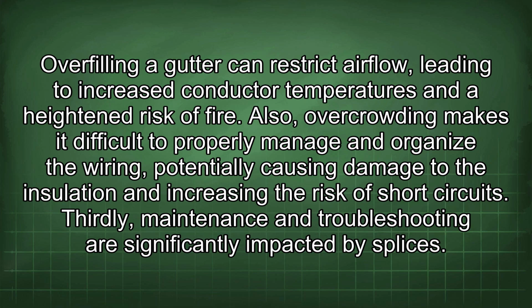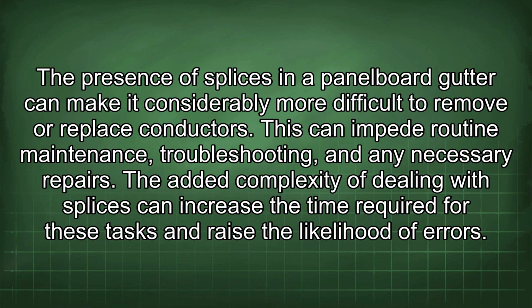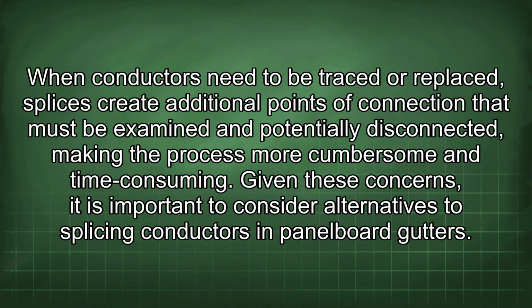Thirdly, maintenance and troubleshooting are significantly impacted by splices. The presence of splices in a panelboard gutter can make it considerably more difficult to remove or replace conductors. This can impede routine maintenance, troubleshooting, and any necessary repairs. The added complexity of dealing with splices can increase the time required for these tasks and raise the likelihood of errors. When conductors need to be traced or replaced, splices create additional points of connection that must be examined and potentially disconnected, making the process more cumbersome and time-consuming.